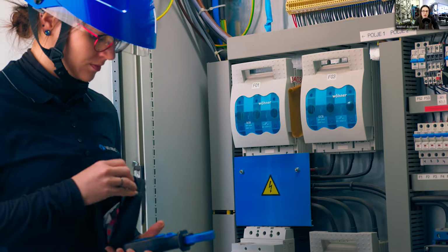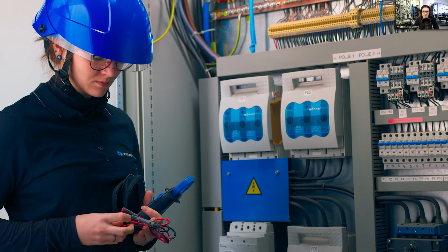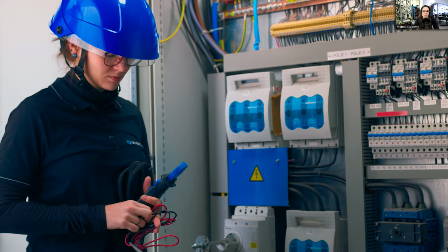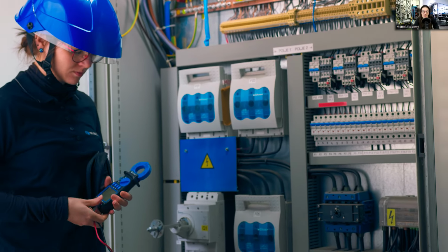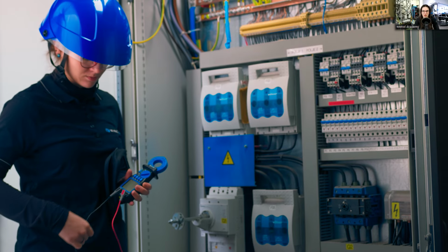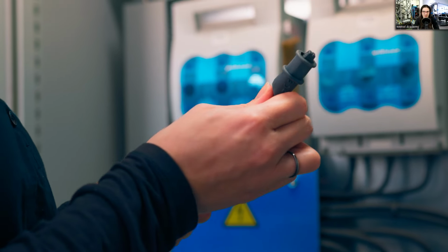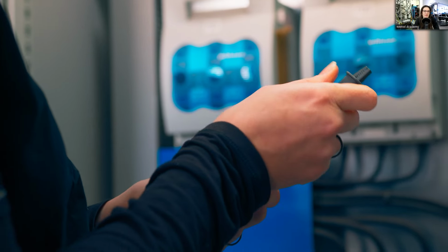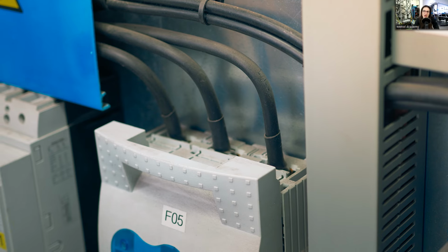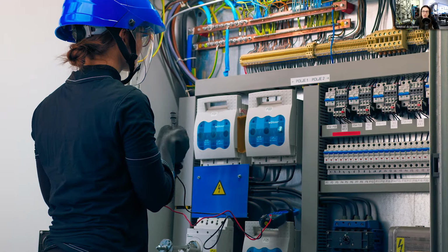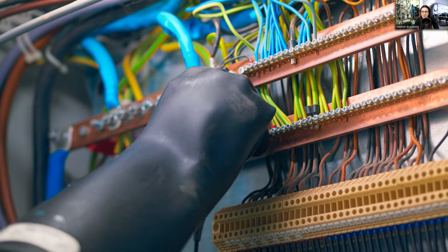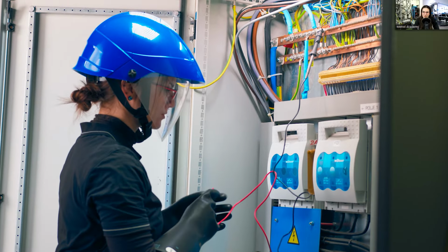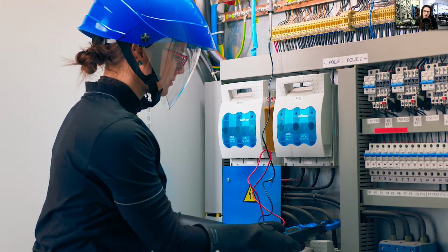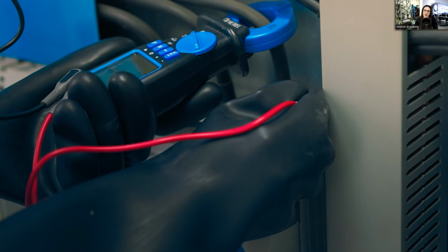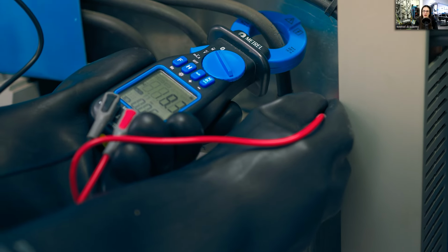This is again an industrial distribution board. So I'm going to use the probes and clamps to connect to the neutral or to the PE. And I will be using the clamps and the other probe to measure power on each phase. The measurement should be done on all three phases so that we can compare results on them and look for any imbalance in them.